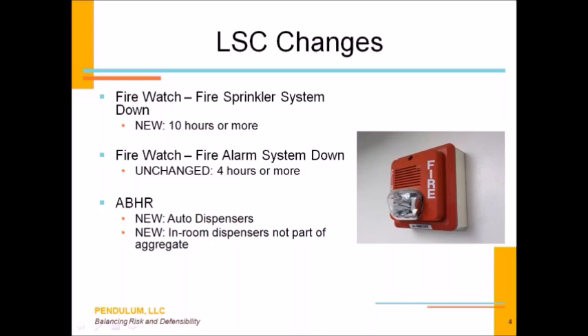But when it comes to the overall presence of ABHR in the smoke compartment, you do not need to include the ABHR devices that are in a patient or resident room. So the volume in the resident or patient room is not considered part of that 10-gallon aggregate limit. So you need to make sure that you comply with the elements of spacing, that you don't have them near electrical components like light switches and electrical outlets. And the codes are pretty prescriptive about that. But in general, you're allowed to have more of these devices, but they cannot exceed 10 gallons per smoke compartment in the common areas or the means of egress.